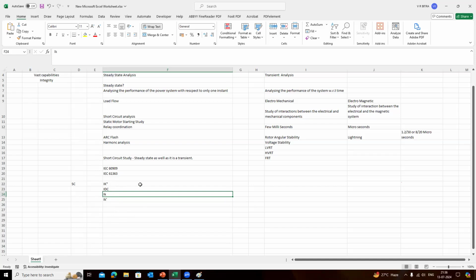Irrespective of the instant at which the fault has happened, the steady state current IK will remain the same, and all other components will be different, including the IDC. The DC component also will change with respect to the instant at which the fault has happened. So the DC fault current will change your asymmetrical current, which will change this IK double dash and IK. That means the entire wave shape of the fault current itself will be different. And after that, the system settles down.